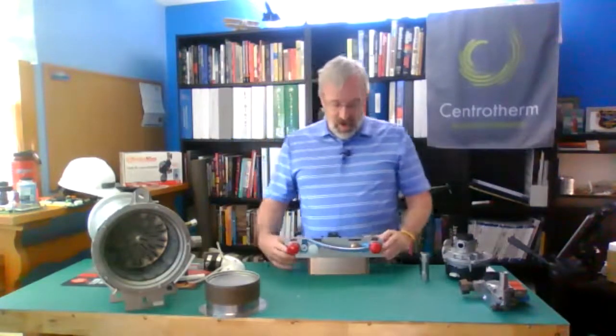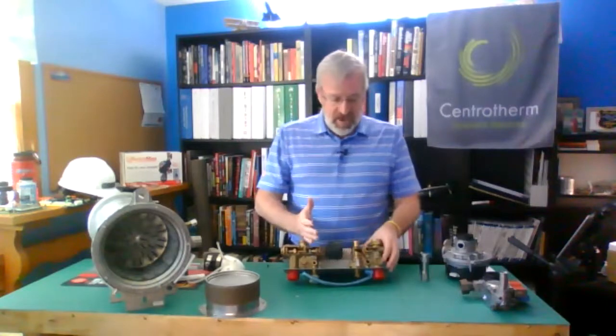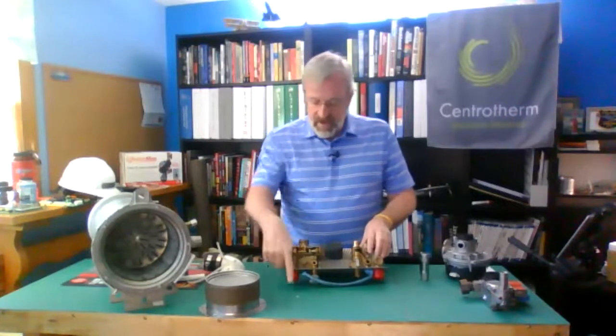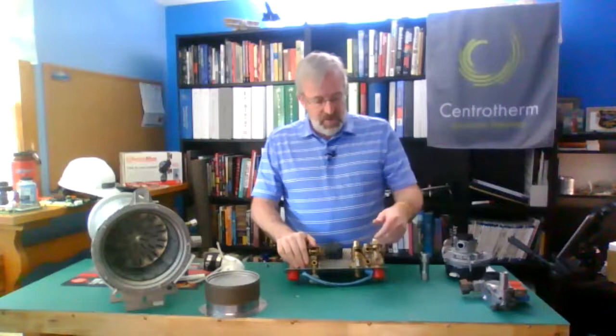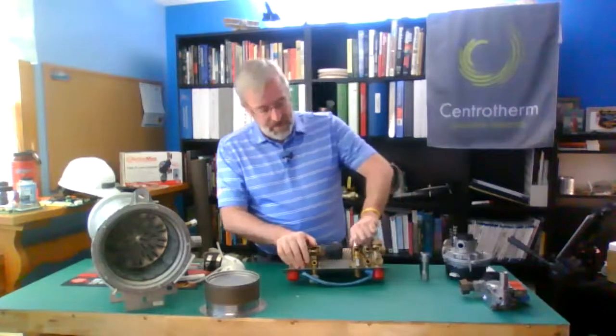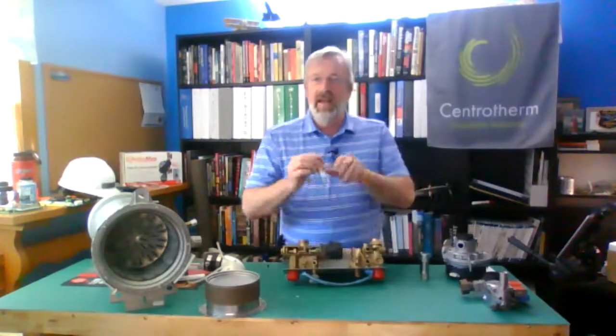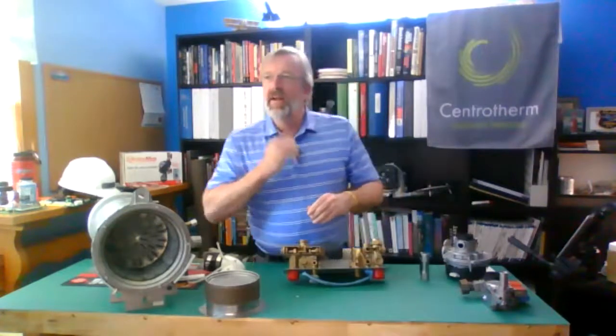Now, how does this guy work? So pretty simple. I'm the heat exchanger on this side, connected into it, big barrel heat exchanger right now. And what I'm going to do is my water coming out of my heat exchanger, my heated water, is going into here. On a typical call for heat, it diverts and goes out to the system. Water comes back from the system out to my boiler. I get a call for domestic, which is triggered right here. My potable water comes in this side. In here, you guys can hear that. That's my switch. It's a magnetic switch, and on top is the sensor of it. So as that raises, when I get that 1/3 of a gallon of water, it triggers my domestic hot water call.